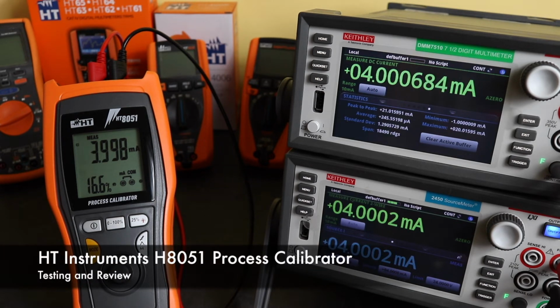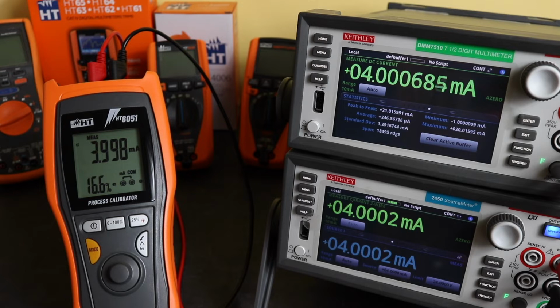Hope everybody's doing well. And today we're on with our HT8051 Process Calibrator. Now these instruments are specialist instruments. They do have very limited functionality, but they do that functionality very well and very accurately. Now this particular instrument can either supply or measure 0 to 10 volts, or it can supply or measure 0 to 24 milliamps. In terms of accuracy, on all the ranges that it has is 0.02% plus 4 digits.